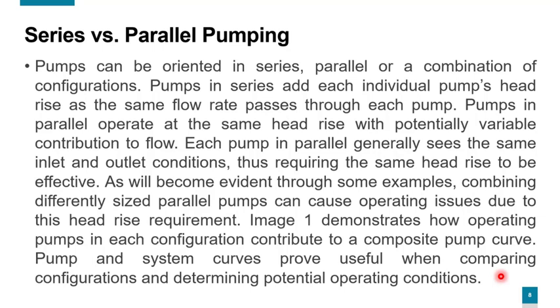Combining differently sized parallel pumps can cause operating issues due to this head rise requirement. As we've seen before, image number 1 demonstrates how operating pumps in each configuration contributes to a composite pump curve. Pump and system curves prove useful when comparing configurations and determining potential operating conditions.